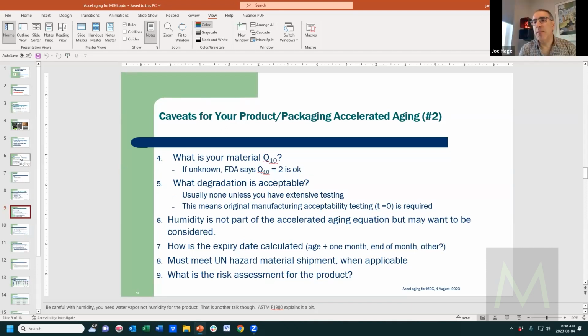How well does accelerated aging mirror real aging historically? It's correlated, but it depends upon your materials, and that's why you have to do real time at the same time, because you might have picked the wrong temperature. I've seen that. And what we've done, especially when I'm working with class 3 devices, is look at every single material in the product and the packaging and do our research on what temperatures might affect that. And if we don't know, that's when we do some engineering tests and look at different temperatures and what it's doing to the package itself.